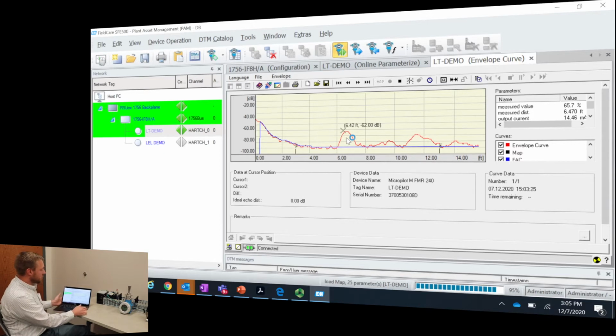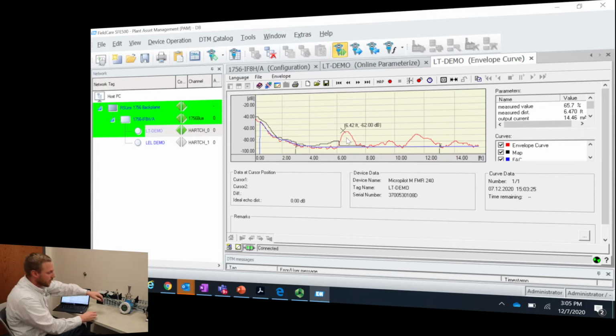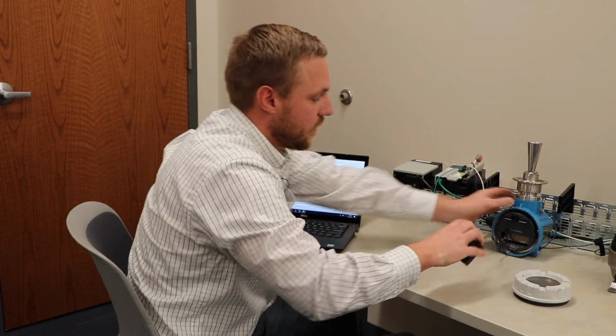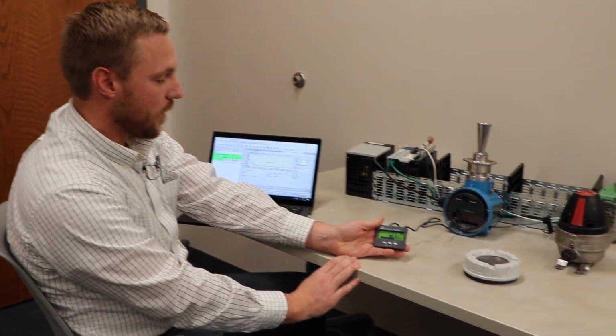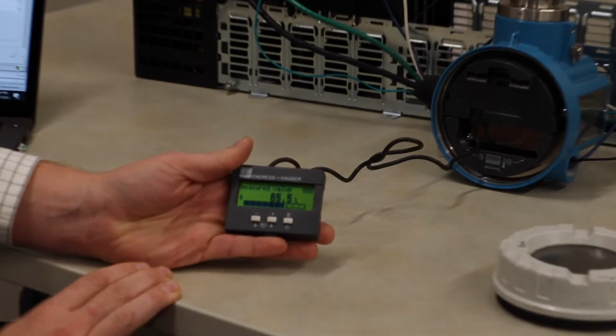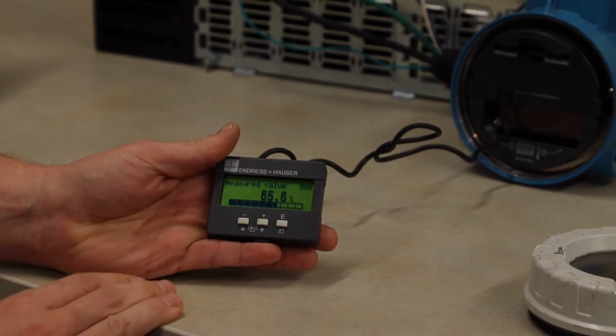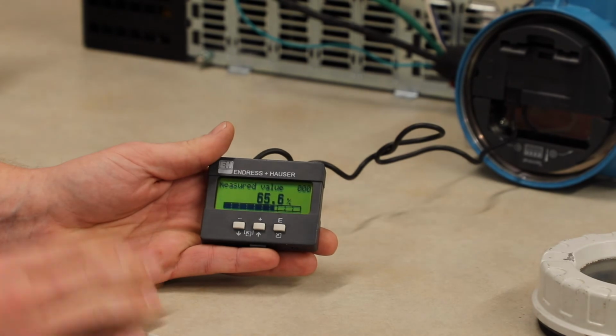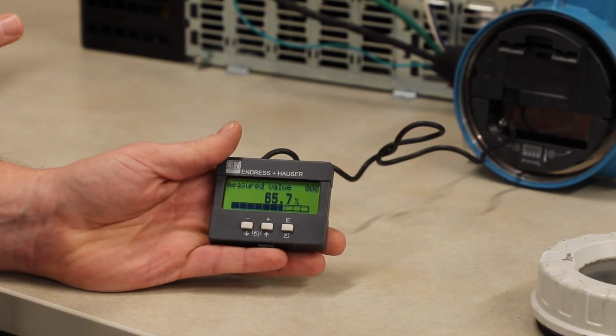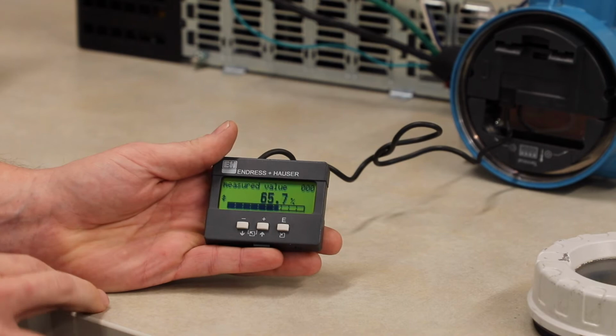If we were to tilt the radar, we would see the reading on the radar change. We would actually also see this red line change as well. We would have to re-pull in that echo to see that. But just to show you how this responds, I'm going to tilt the radar so that we can see a different reading. Right now we have 65.4% of our measured value. You'll notice it changed a little bit there. I have it on fast change. It actually detected the slight push I gave it as I pulled this out.